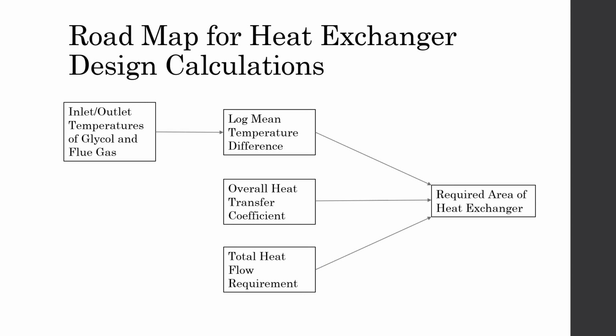The Guelph stack heat exchanger must be designed so that it is able to supply the required heat. As discussed earlier in this presentation, the heat exchanger must transfer 71.9 kilowatts of energy. In analyzing the heat exchanger, the main value that was to be calculated was the total surface area required of the heat exchanger. The area is dependent on the overall heat transfer coefficient, the total heat flow required, and the log mean temperature difference of the two working fluids.